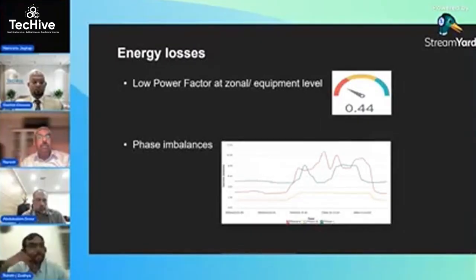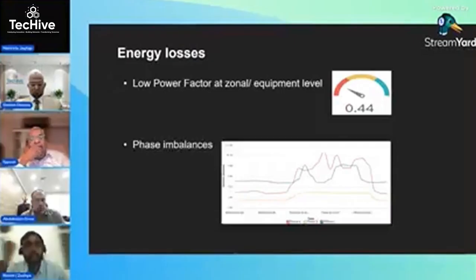A typical easy tip to pick out energy losses is if you have a low power factor, meaning you're not utilizing the power being procured at that equipment level. If you're able to measure that at a zonal or equipment level, that could give you a better idea.